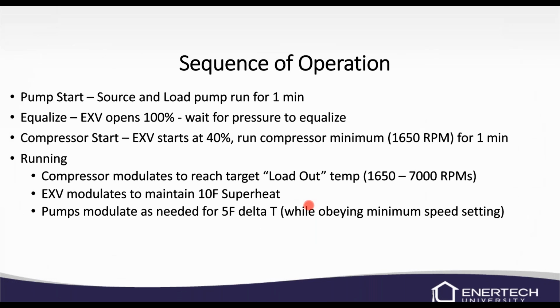I'm sure you're going to need to know the sequence of operation. It's pretty important when you're trying to troubleshoot things. On the screen, it will tell you what state it's in. The first thing that's going to happen when it receives the call is it's going to say pump start. The source and load pumps are going to run for about a minute, and you'll start to see some flow. It'll show you your percentages, things like that.